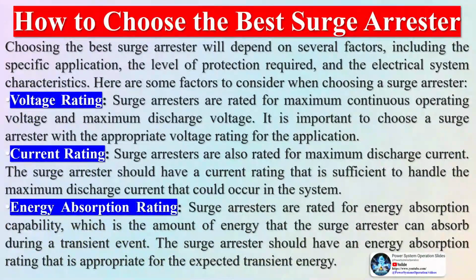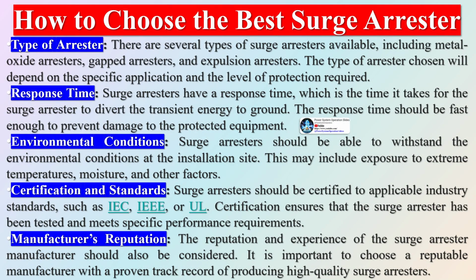How to choose the best surge arrestor? Choosing the best surge arrestor will depend on several factors, including the specific application, the level of protection required, and the electrical system characteristics. Here are some factors to consider when choosing a surge arrestor. Voltage rating. Surge arrestors are rated for maximum continuous operating voltage and maximum discharge voltage. It is important to choose a surge arrestor with the appropriate voltage rating for the application. Current rating. Surge arrestors are also rated for maximum discharge current. The surge arrestor should have a current rating that is sufficient to handle the maximum discharge current that could occur in the system. Energy absorption rating. Surge arrestors are rated for energy absorption capability, which is the amount of energy that the surge arrestor can absorb during a transient event. The surge arrestor should have an energy absorption rating that is appropriate for the expected transient energy.